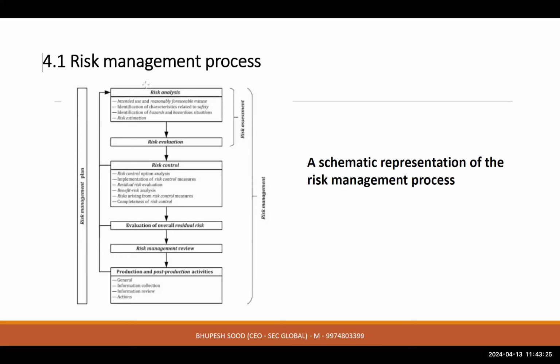Once you have analyzed the risk comes risk evaluation. Once the team has done the risk evaluation, there is a step of risk control. Once you have done the risk controls, you identify the residual risk, that means the risk which still remains. Then a risk management review, a stage where you think of whether you would like to release the product or not. Once you have decided to release it, there are post-production reviews: what you learn from your product in the market, and from the competitor's product in the market.